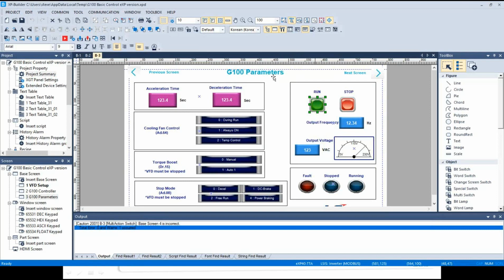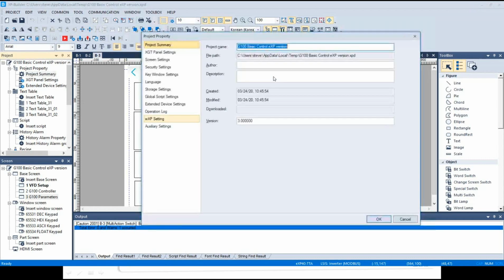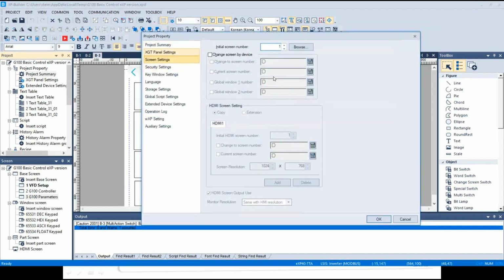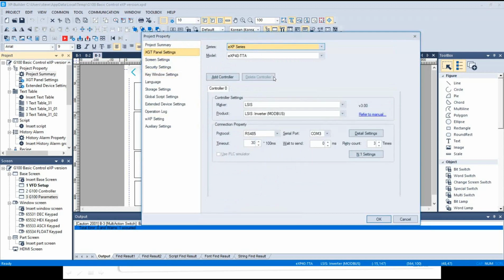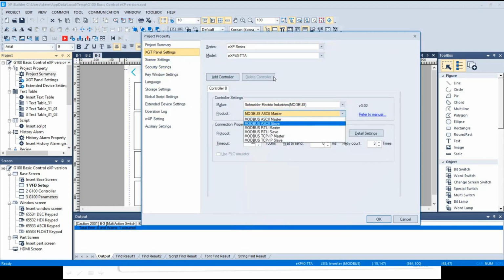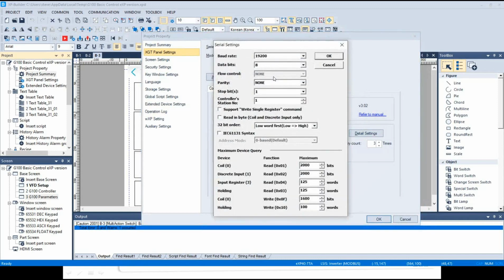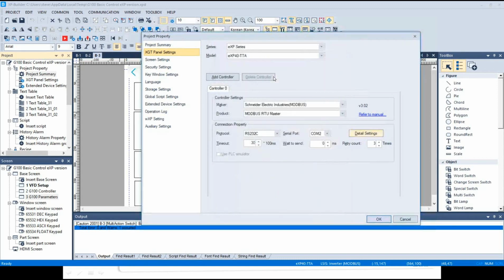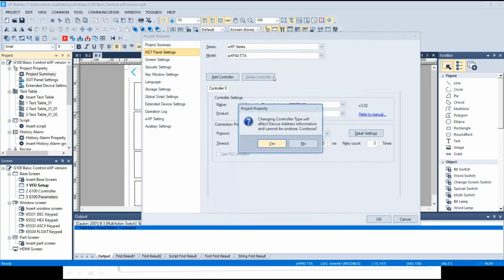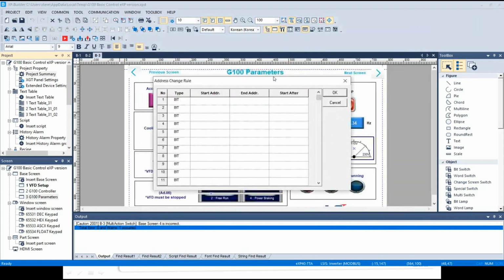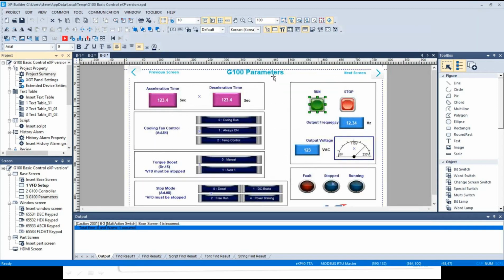But let's say I'm using some brand X VFD, I would go in there and change this a little bit. I wouldn't use the LS controller. I would use the generic Schneider Electric Modbus Master RTU. You could hit details and change your baud rate, your data bits, your parity, your stop bits, and so on. Right now it's going to change my whole project and try to map it all.